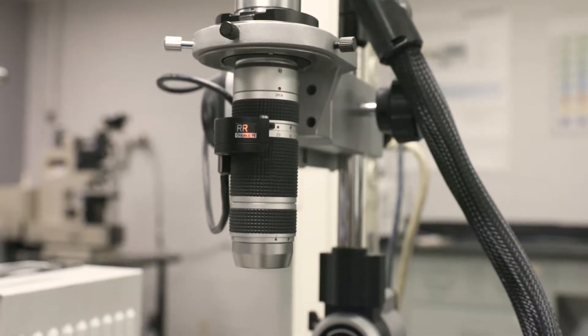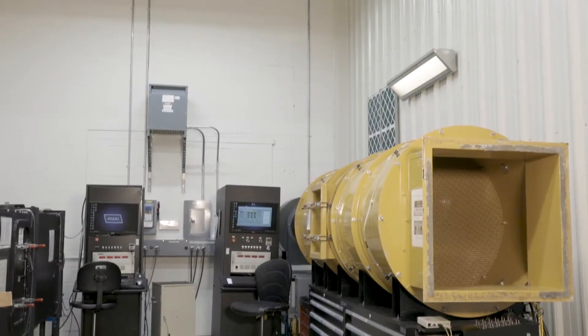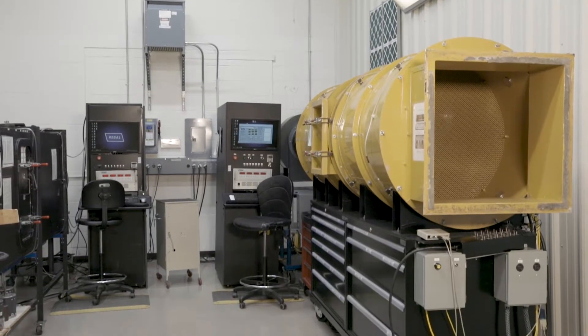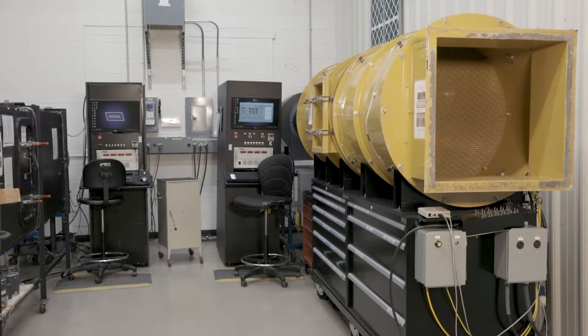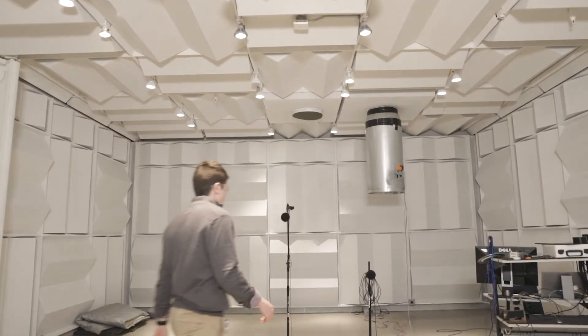Some of the testing we are able to perform are reliability and life tests, airflow with chambers that range from 50 to 5,000 CFM with static pressure ranges from 0 to 4 inches of water column, and sound tests in our semi-anechoic or full-anechoic chambers.